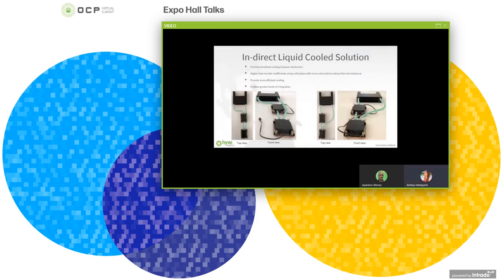Today's discussion will be focused on indirect liquid cooling. Images on the left and right show the cooling solution that is applicable to 2-socket, 4-socket, and 8-socket configurations. A typical liquid cooling loop comprises cold plates used in conjunction with pumps, a heat exchanger, and tubes to circulate the liquid or coolant. In most cases, reservoirs and valves are used to control fluid volume and flow rate, and for this solution, reservoir tanks were added to account for any coolant loss over time.